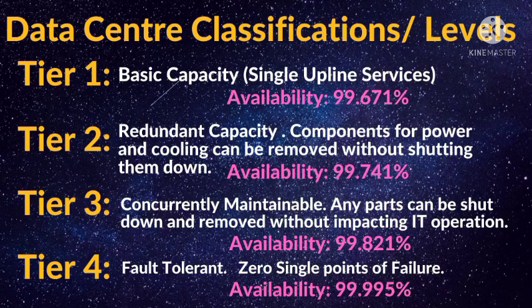Availability of this data center is 99.741%. Tier 3, concurrently maintainable, any parts can be shut down and removed without impacting IT operation. Availability is 99.821%. Tier 4, fault tolerant, zero single points of failure. Availability is highest, 99.995%.